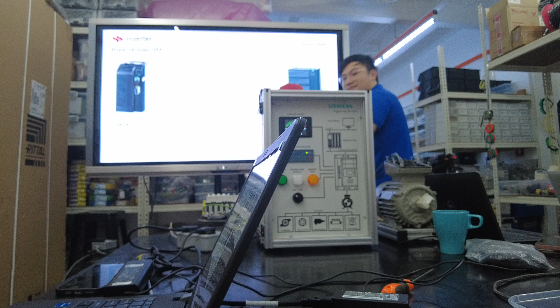The voltage one way, current also is one way. If IGBT two way means if you got some energy generated, backfeed from your motor back to your DC link, they can backfeed back to your power line for power saving purpose. Because when the motor tries to slow down, when the motor is driving the drive, not the drive driving the motor, they will become a generator. Your power will become negative.